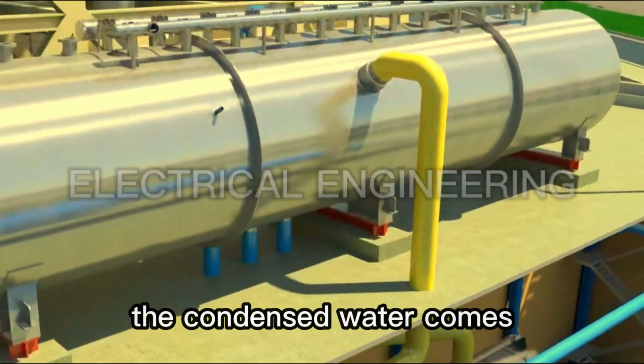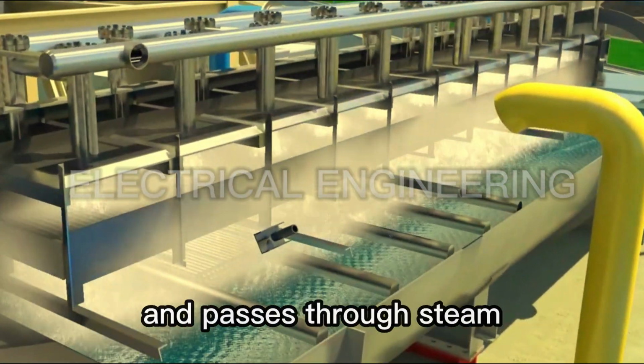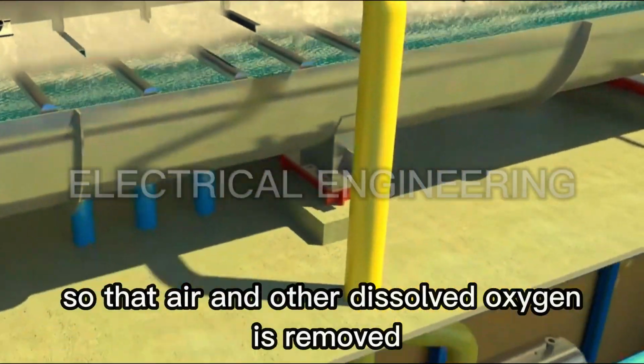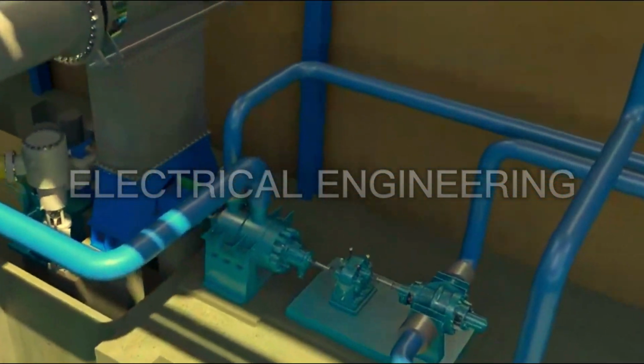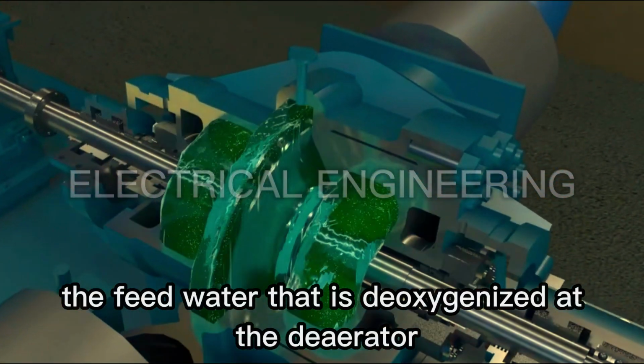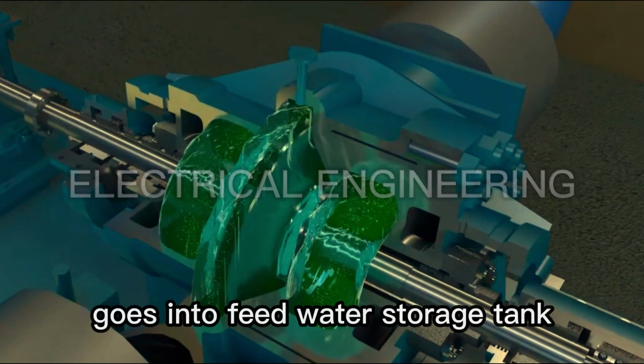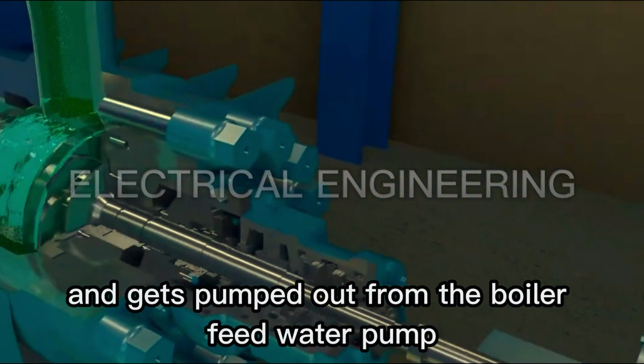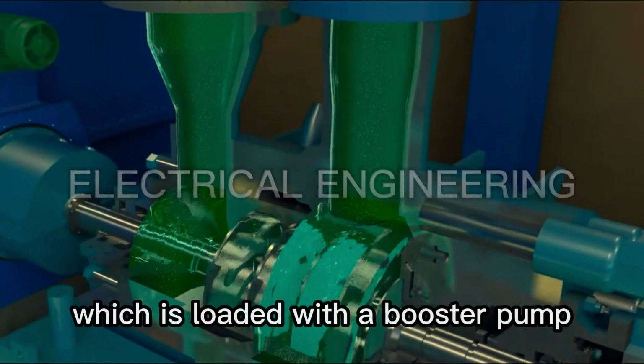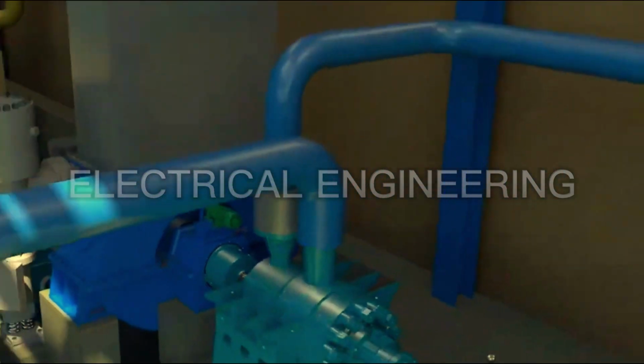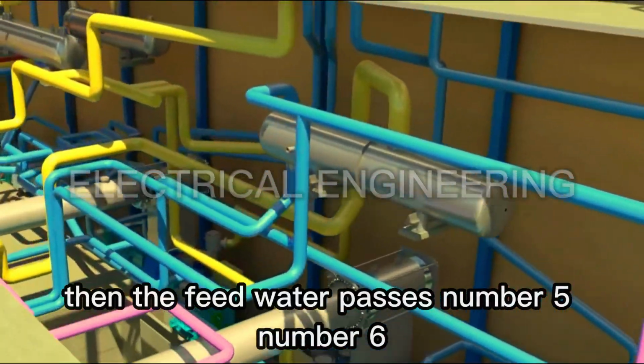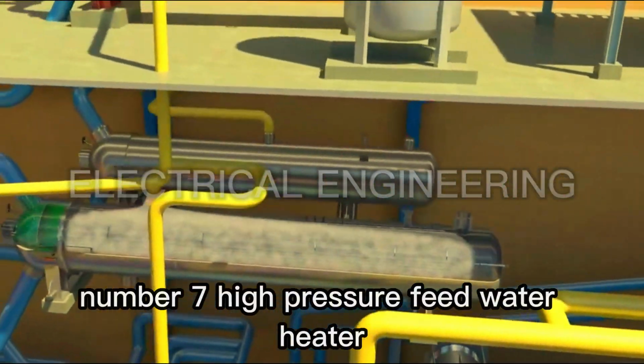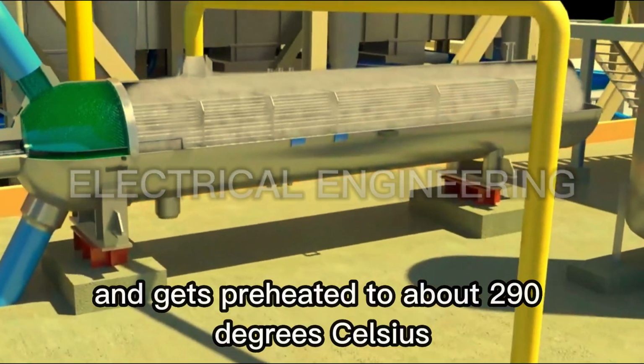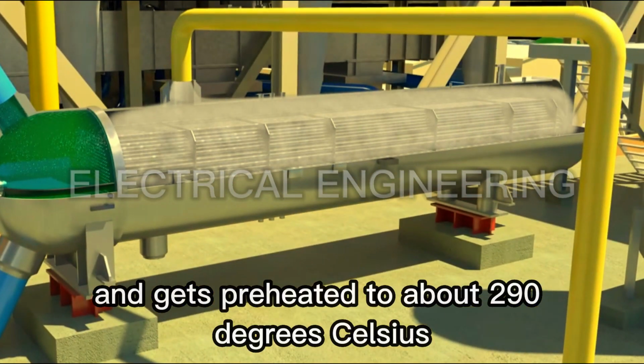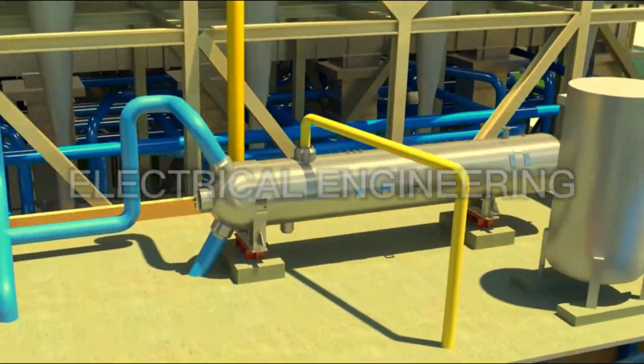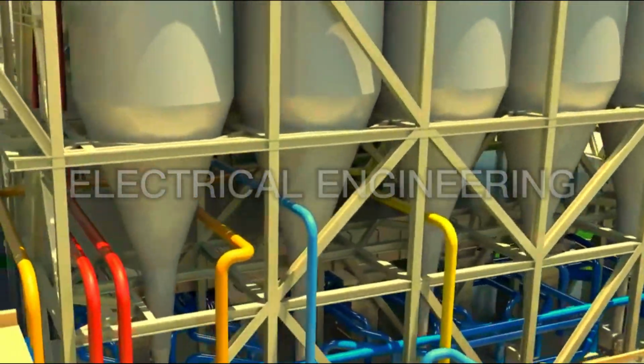The condensed water comes out of the upper tray of the deaerator and passes through steam so that air and other dissolved oxygen is removed. The feed water that is deoxygenized at the deaerator goes into feed water storage tank and gets pumped out from the boiler feed water pump, which is loaded with a booster pump. Then the feed water passes number 5, number 6, number 7 high-pressure feed water heater and gets preheated to about 290 degrees Celsius when rated load and is sent to the economizer of the boiler.